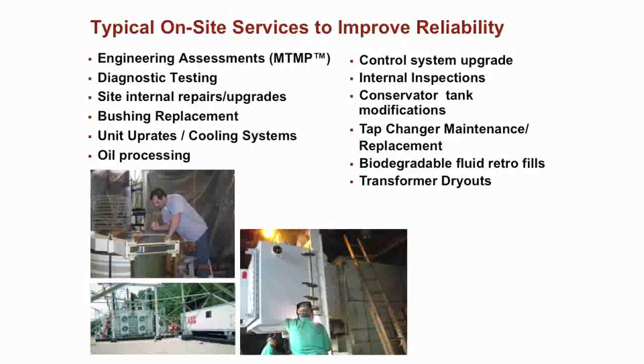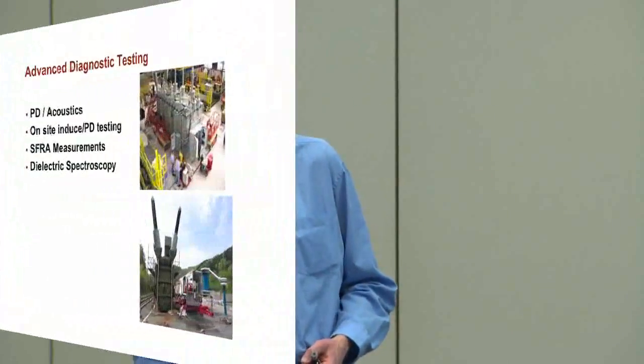And doing tap changer maintenance or replacement of a tap changer. In some cases, you can have a tap changer that is so old that it's no longer supported, and it becomes more practical just to replace it with a modern model. Another thing we see is replacing the oil with a more biodegradable oil, or totally biodegradable oil, and then drying out a transformer. This is where you remove all the moisture out of the cellulose, so that first of all you reduce the aging rate, and then you can extend the life of the transformer quite a bit. I'll just go quickly through all these with a little more detail on each.